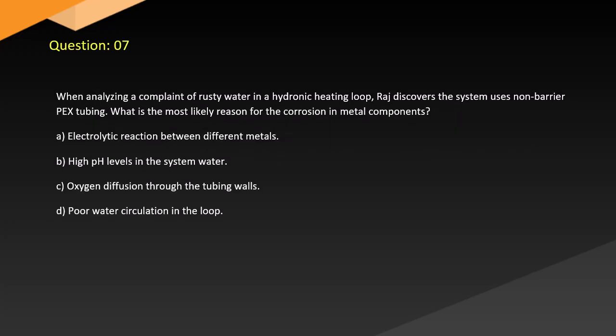Question 7. When analyzing a complaint of rusty water in a hydronic heating loop, Raj discovers the system uses non-barrier PEX tubing. What is the most likely reason for the corrosion in metal components? A. Electrolytic reaction between different metals. B. High pH levels in the system water. C. Oxygen diffusion through the tubing walls. D. Poor water circulation in the loop.